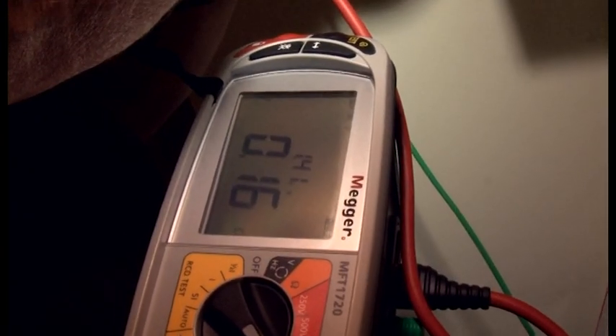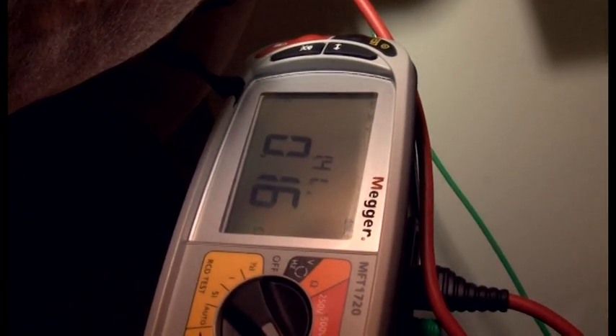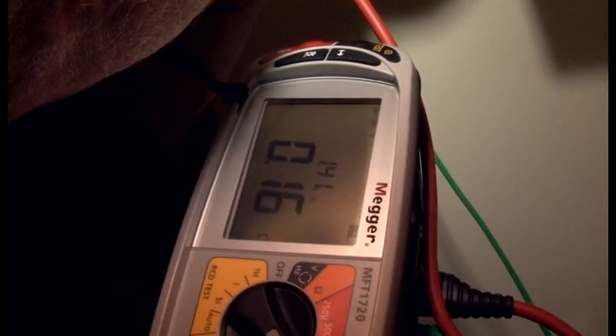Now the reading I've got here is 0.16 ohms and 1.41 kA. A quick word about the reading of fault current. It's important to realise that this is actually a calculation based on the nominal voltage, in this case 230 volts, divided by the impedance reading. It's not based on the actual voltage at the time of test, and it's not measuring current.